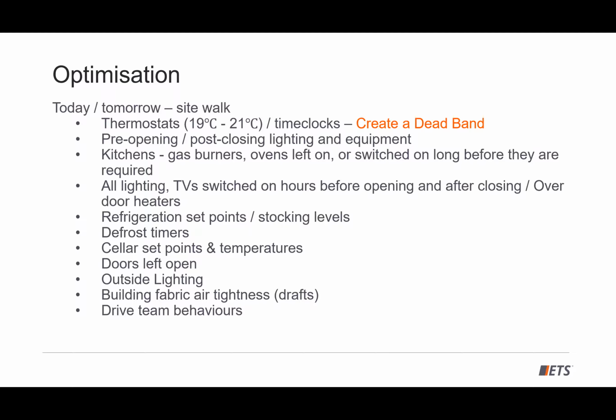For instance, in a lot of commercial real estate offices, we keep the heating off until we see it's needed, because people are coming in from outside, taking their coats off, and they generally warm the place up anyway. We won't bring the heating on until it's needed, and then warm the place up. Similarly, we might turn the heating off at 3 or 4 o'clock if it's open till 6, creating that dead band and the shoulders so we can creep everything back without affecting the operation of the facility, because people going home don't notice it's getting colder - they'll put their coat on in a minute and go home. So we're tailoring it off through the day.